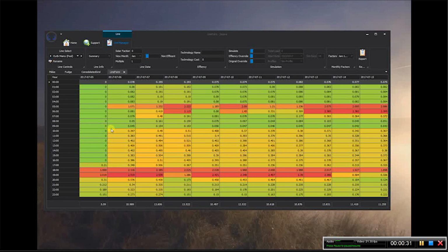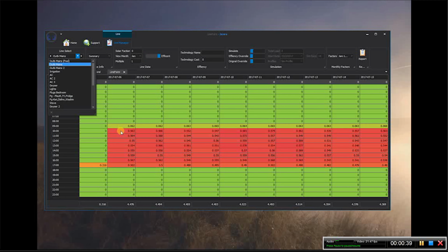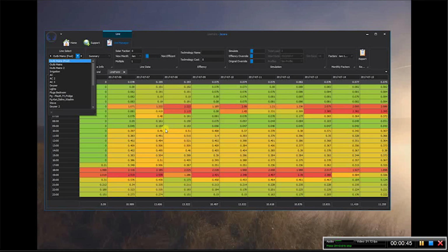And then the pool pump is on from 10 to 5 in the afternoon. We can confirm the pool pump times by looking on the second phase of the pool pump. You can see from 10 to 6 in the evenings. That is when the pool pump's running. So we've got the problem that if we use a solar fraction for reducing the pool pump, everything would be reduced by that solar fraction.